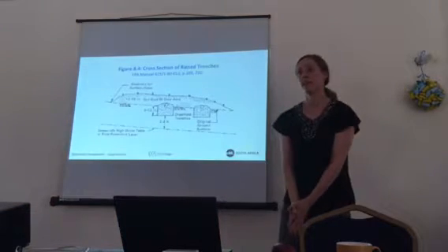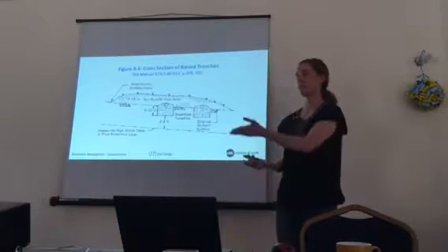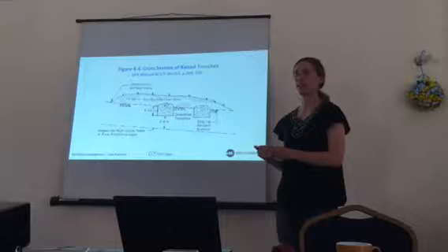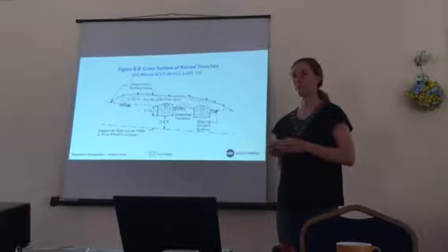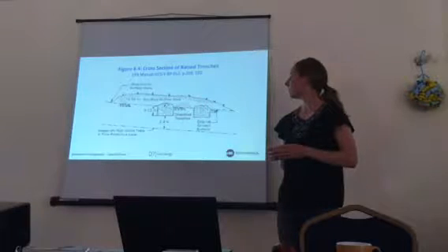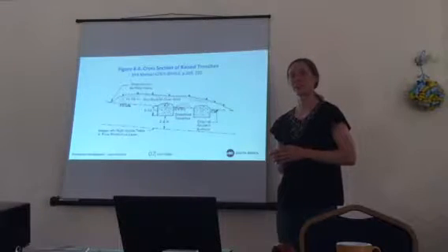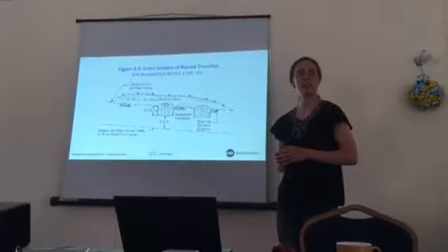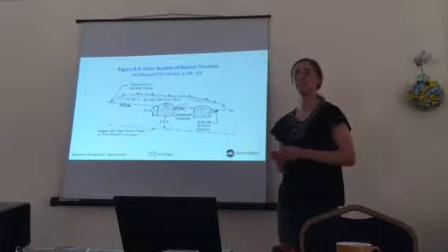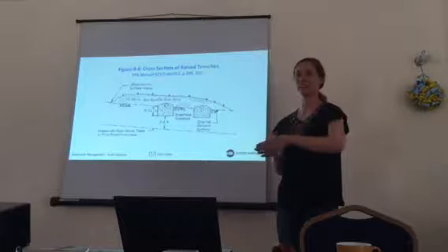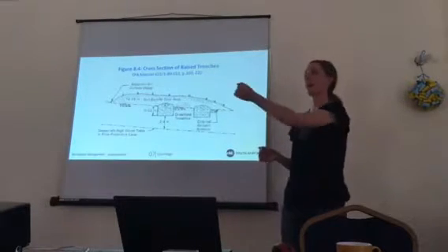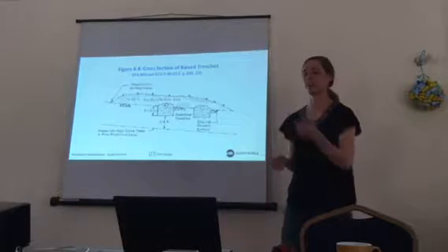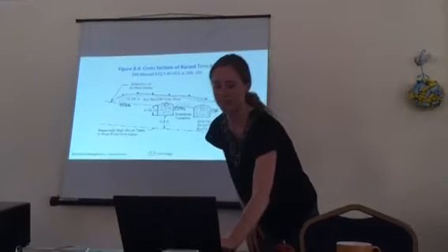It's for both. So the gray water is coming out of the tank, and then the black water coming from the toilet specifically. And you can have it that high? The septic tank is the primary treatment and it separates out the solids and the floaters. So this is the liquid coming out of the septic tank after it's gone through the primary treatment. This is the secondary treatment.